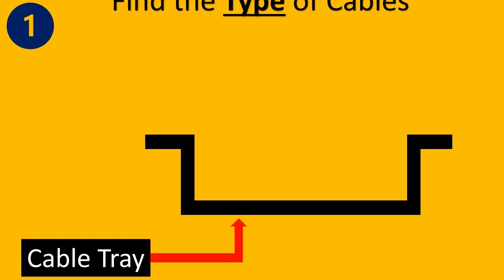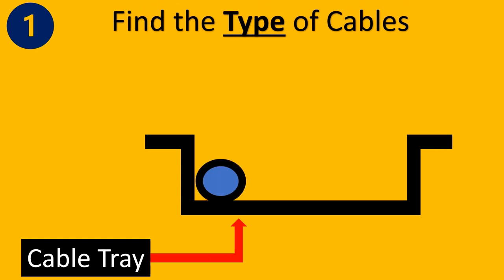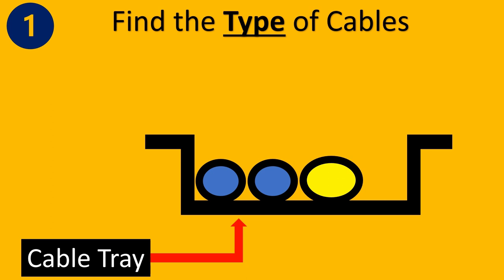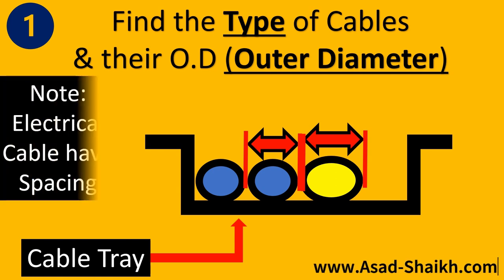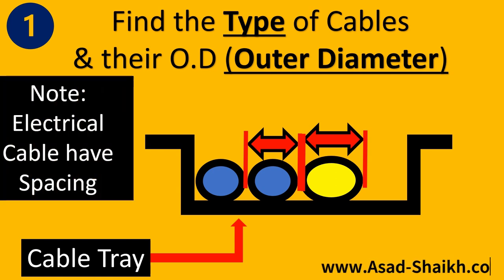Step one: imagine this is your cable tray. The first thing is to know the type of cables entering the cable tray — for example, analog input, digital input cables, etc. — and their outer diameter (OD). We need to find the OD from the catalogs. Also note that for instrument cable tray sizing versus electrical cable tray sizing, certain spacing needs to be kept because electrical cables carry very high current. For our purposes here, this is not applicable.